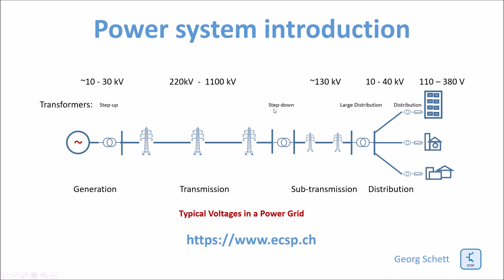Then you have step-down transformers bringing the voltage down to 130 kV, which is a typical sub-transmission network built around larger cities. Then large distribution transformers feed distribution networks at voltage levels between 10 to 40 kV. Finally, smaller distribution transformers feed appliances and homes at the voltage level well known to us: 110 to 380 volts.